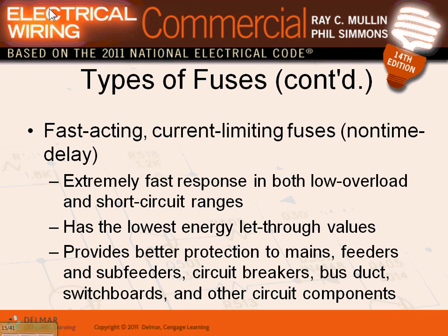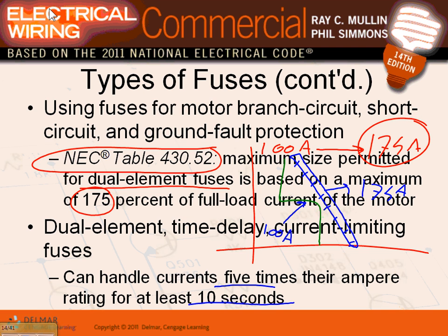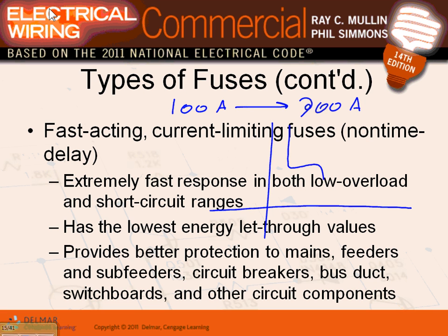Fast acting fuses, those guys don't have any delay whatsoever. Actually, this almost looks like a fast-acting fuse, the one I drew. Fast-acting fuses, guys, are non-time delay fuses. If you remember, for a 100 amp motor, we put a 300 amp fuse. Here's my 100 amp motor. If I put a fast-acting fuse, it's going to look very sharp. Oops, I don't want it to overlap. So it's going to go all the way up to here and back.